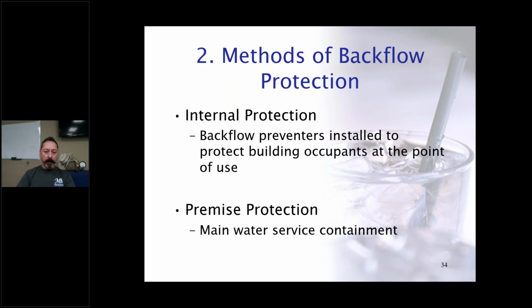The other type of isolation method is something called premise isolation or protection. And that's a containment type of installation where you install a backflow preventer on the main water service, and that isolates that particular facility from the distribution system. So it doesn't necessarily protect the occupants of the building, but it will isolate that substance from spreading throughout your community, and it is also mandatory by the plumbing code for any severe hazard classification buildings. So we have to have a backflow preventer on severe hazard facilities as premise isolation.